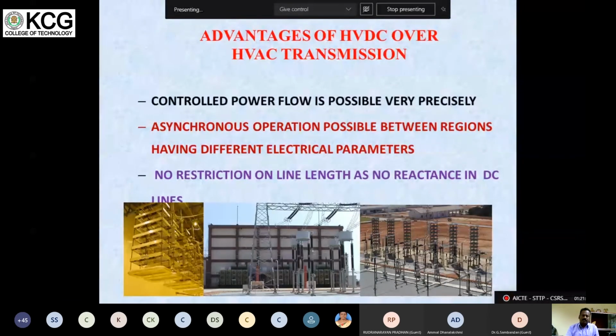Advantage: control of power flow, and asynchronous tie is possible. Now we have made a single system, a single grid, but earlier, before '91, our electrical regions were operating with different frequencies. When the frequency regions are different, we cannot transfer power with AC lines. So we need a DC line to transfer power from one place to another between different frequency regions. This is also called asynchronous operation or asynchronous tie. So asynchronous power transfer is possible with the HVDC system.